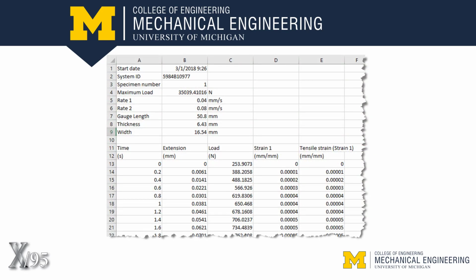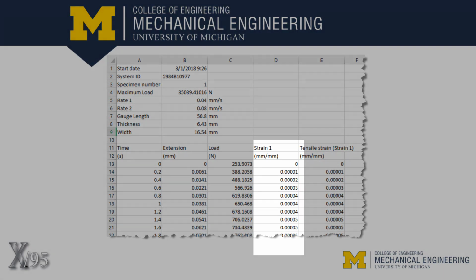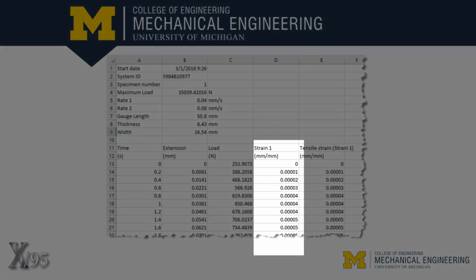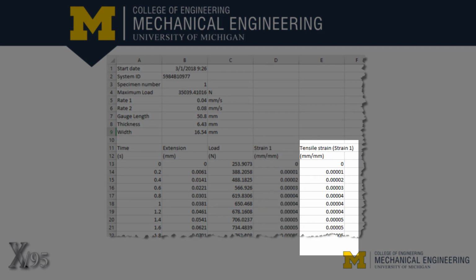Here's a sample data file opened in Excel. The sampling rate is set at 5 Hz with all the time-dependent values listed in columns. The column titled Strain contains the extensometer measurements until the extensometer is removed. The adjacent column, labeled Tensile Strain, contains the calculated strain by establishing a relationship between displacement and strain, which is valid up until fracture.